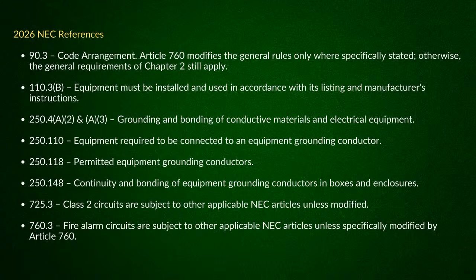It's ridiculous, and this is a good example, because when you look at 250.110, that's equipment that's fastened in place, fixed, or connected by permanent wiring methods. But the one you look at in 250.110 is item 3, where it's in electrical contact with what? Metal.